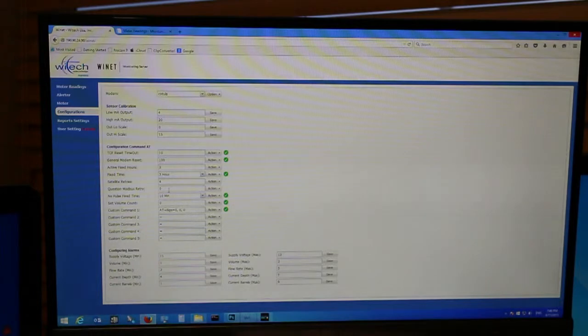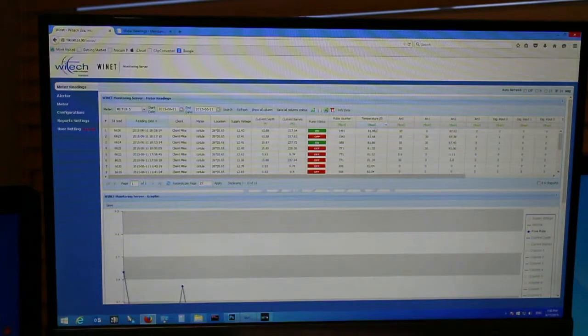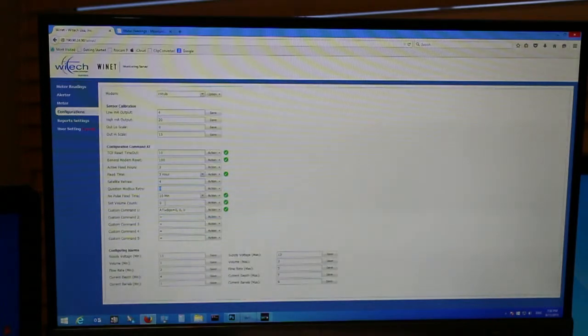How many retries for the Modbus read in case the meter is not responding fast enough, so I have to make retries. I just configure here how many retries, and this is same as fixed time, depending how often I want the report here. So I change it here. If you want to set up either 0 or an exact amount of index count or totalizer, whatever you want, you set it up here. Right now we have 1491. If you want to reset it to 0, then you write 0 here. Okay, and action, you set save.